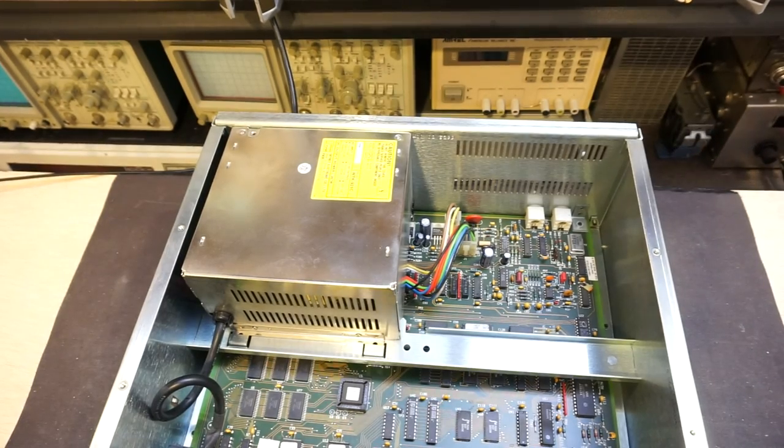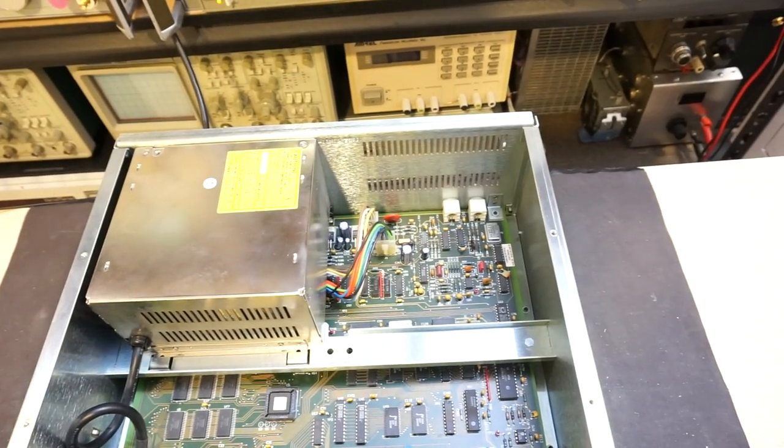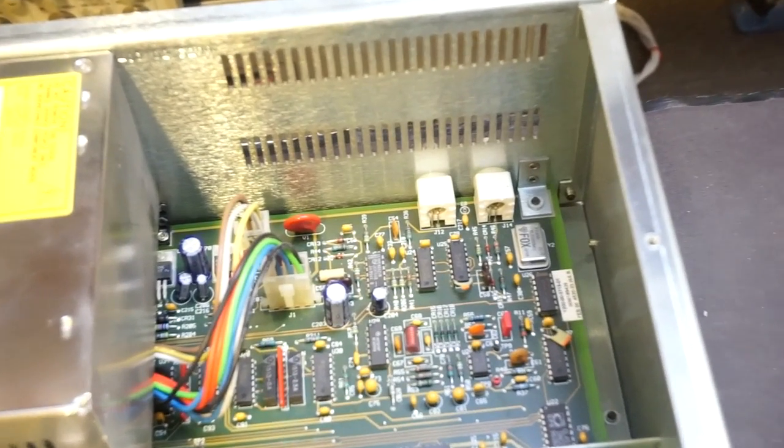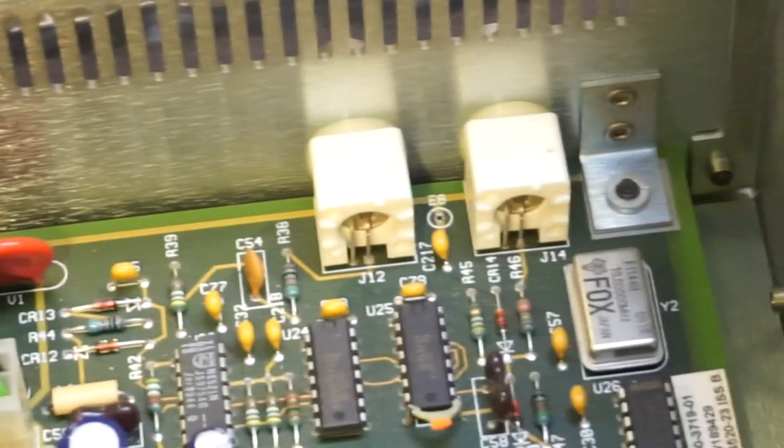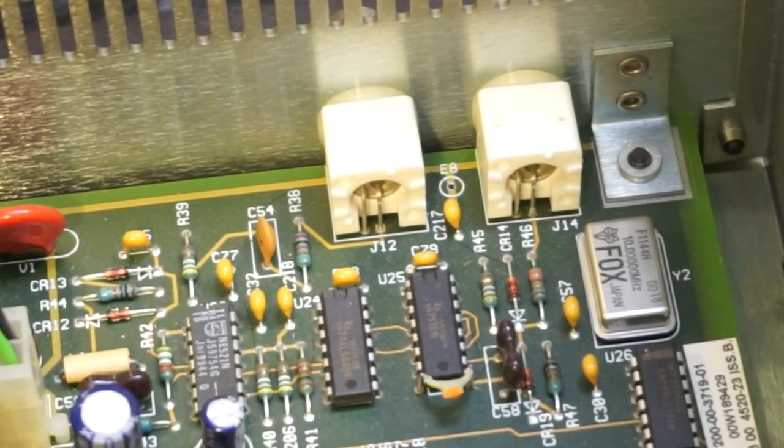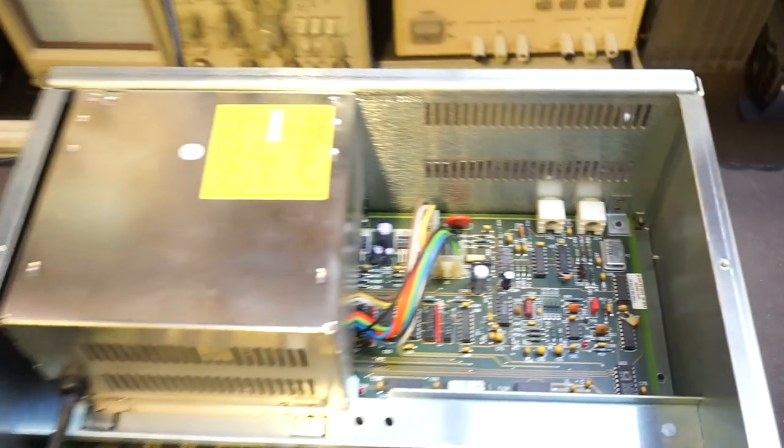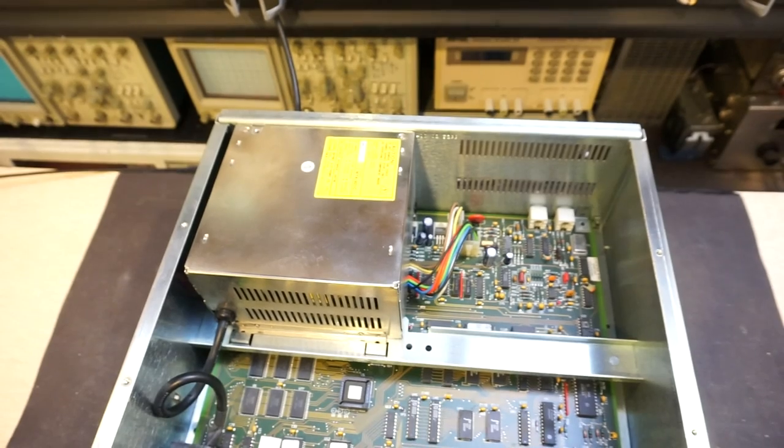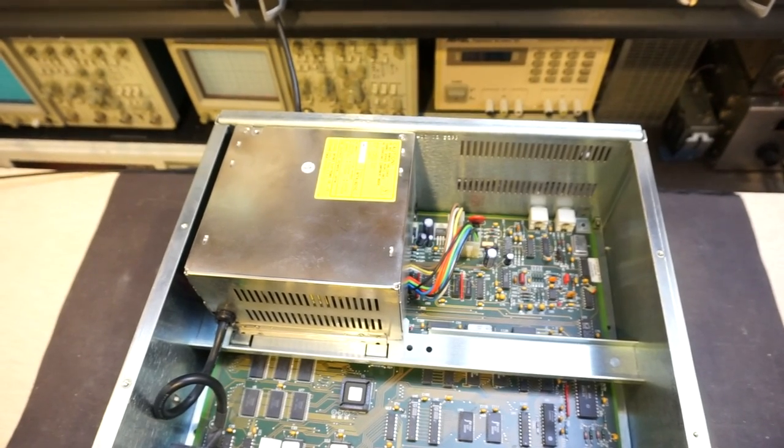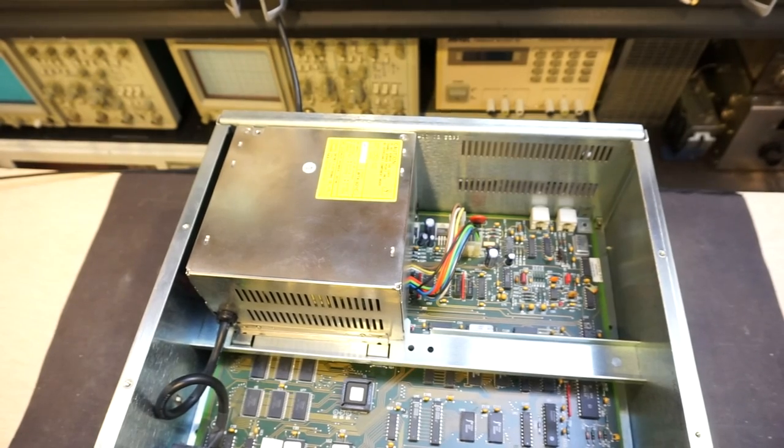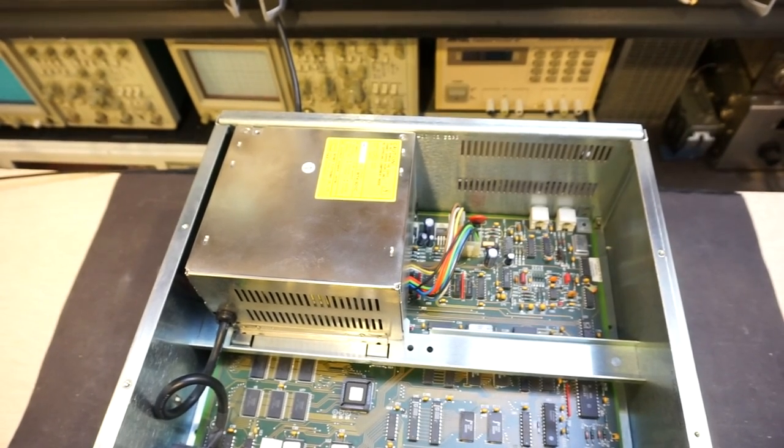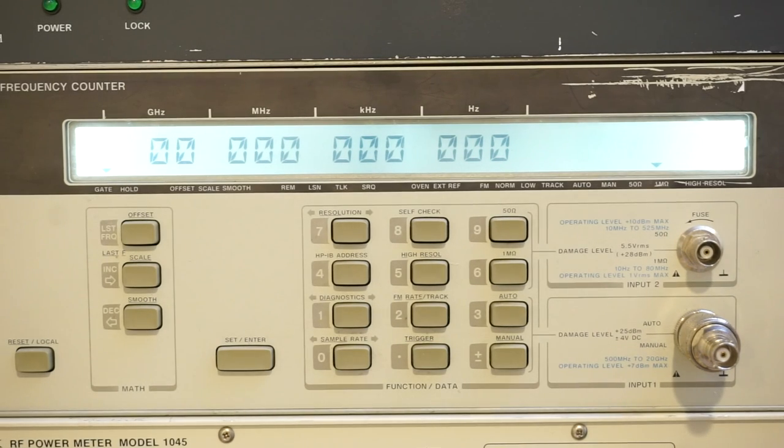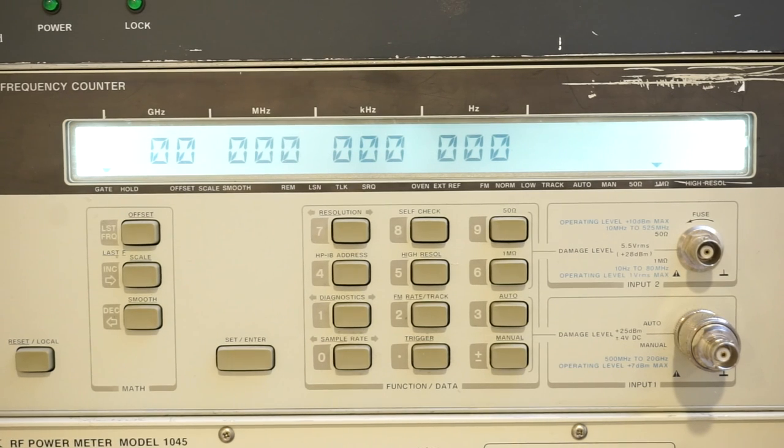I just took the top cover off so you can see the crystal oscillator inside. So that's the metal can sitting right to the rear corner there. And to demonstrate its frequency stability issue, let's turn it on and take a look on the frequency counter to see if I warm it up and cool it down, what frequency changes we're expecting. And for that, I'm going to feed the output signal into this 5350B microwave frequency counter.